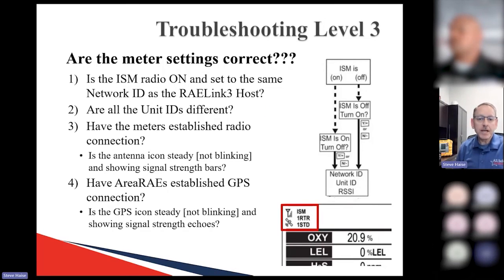This is where we're going to have you check that all the meter settings are correct. Number 1 is your ISM radio on and set to the same network ID as your RAELink3 Host. Again, think of channels on a radio because that's exactly what we're dealing with here: 900 megahertz radios. So we want the network ID on your AreaRAE to match the network ID of your RAELink3 Host. In all my experience, the CST teams are on network 630.